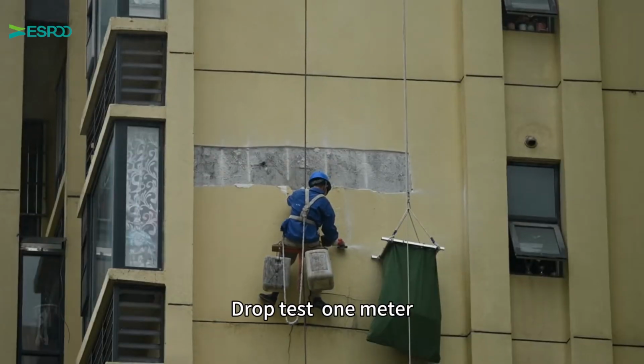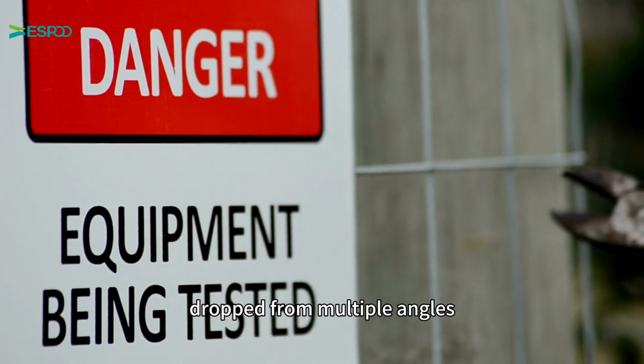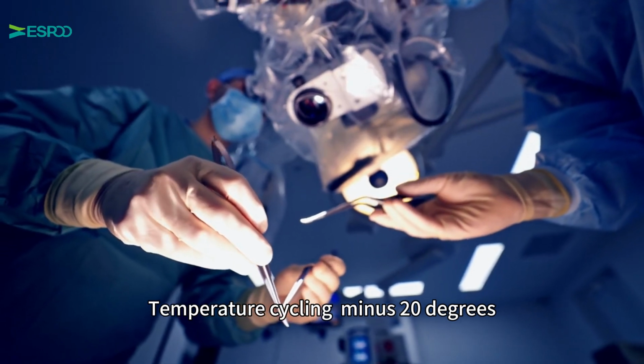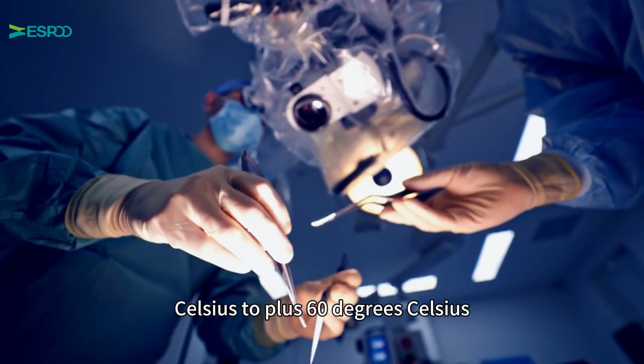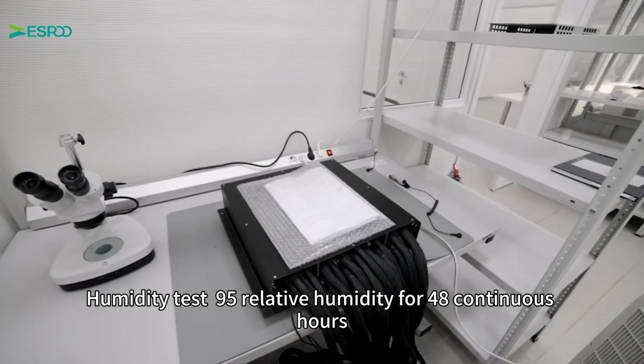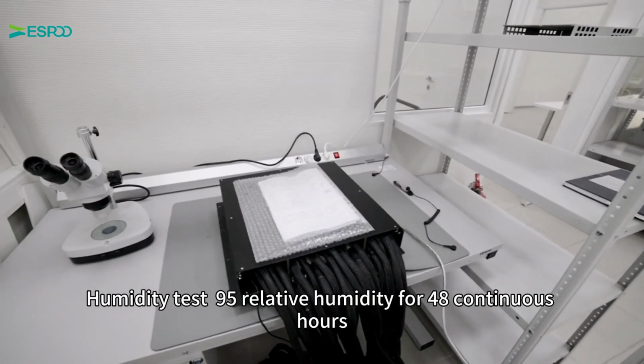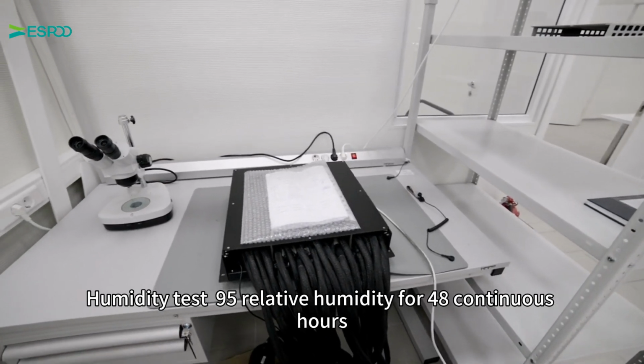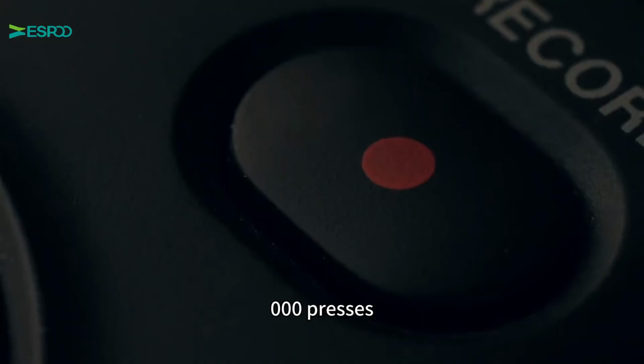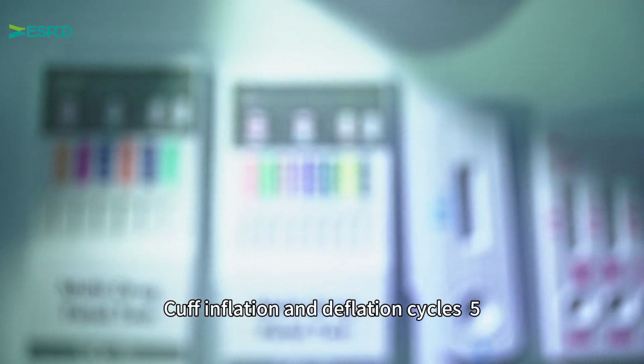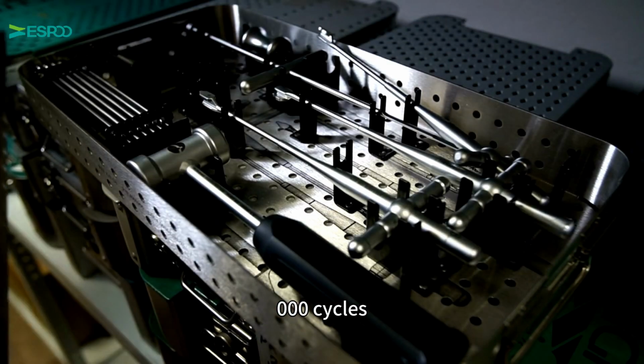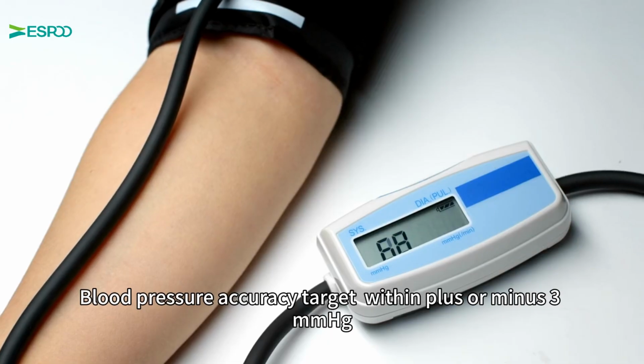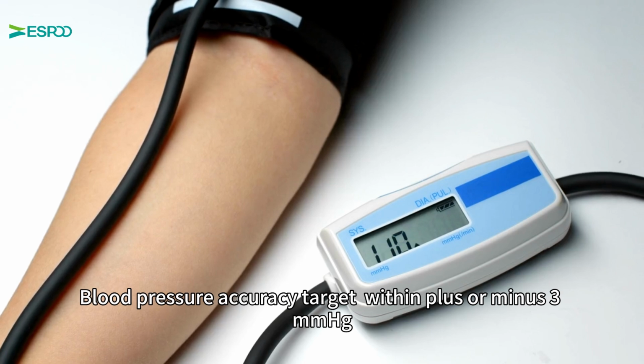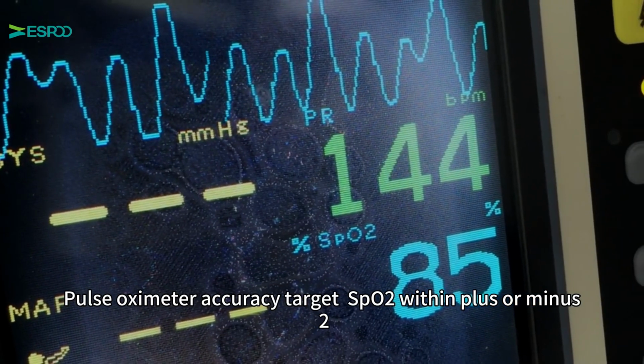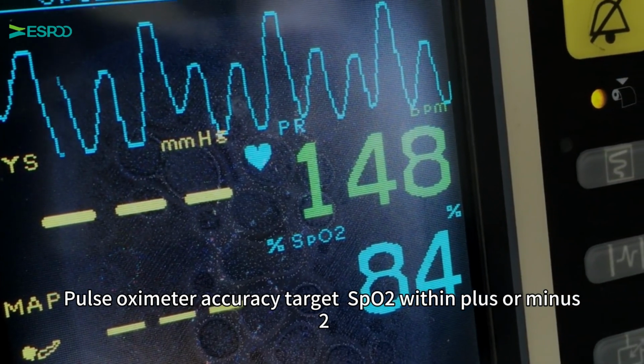Drop test, 1 meter. Dropped from multiple angles. Temperature cycling, -20 degrees Celsius to +60 degrees Celsius. Repeated cycles. Humidity test, 95% relative humidity for 48 continuous hours. Button endurance, 10,000 presses. Cuff inflation and deflation cycles, 5,000 cycles. Blood pressure accuracy target, within plus or minus 3 mmHg. Pulse oximeter accuracy target, SpO2, within plus or minus 2%.